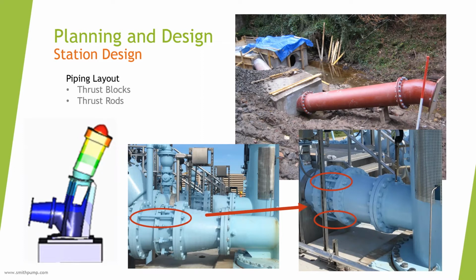We have seen inadequate thrust rods used and still allowed the pump head to move. The AWWA standards for thrust rod sizing is typically not sufficient for pumps, so we tend to upsize them. The bottom is an example found at a job site with only 1 thrust rod used. We replaced this pump for a larger unit and installed at least 4 thrust rods. I believe we actually went back and put more thrust rods on these pumps after testing, but I couldn't find a picture of that installation, so we needed quite a few more.